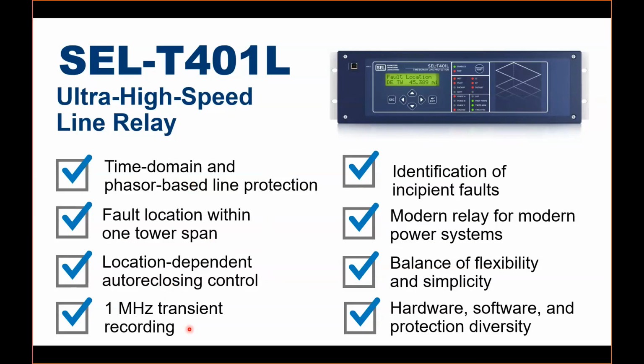This is something that makes this relay different from the conventional technologies, and TD and traveling wave protections are possible because of this very high sampling rate. It can be used as a line monitoring feature, as we discussed, to detect some incipient faults, or the faults that have not happened yet but are about to happen, or we call these precursors or incipient faults as well. And it's a modern relay for modern power systems because of the new induction of renewable energy, inverter-based sources. So we have some challenges with the conventional protections because of low fault level current. So these new technologies can help in that.